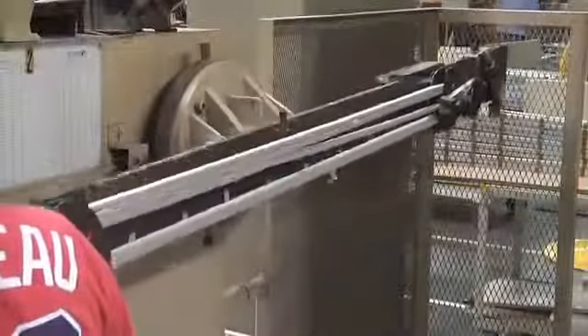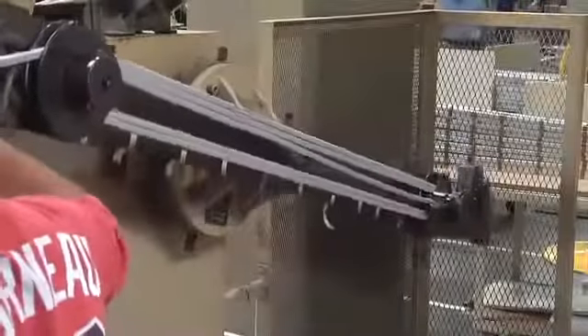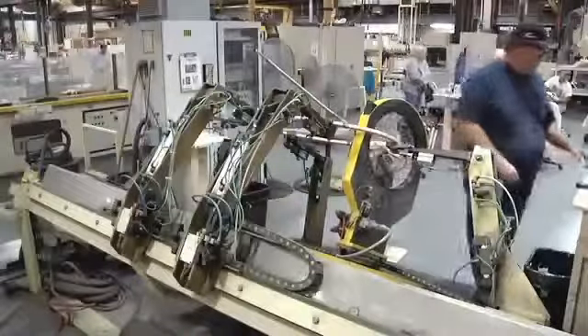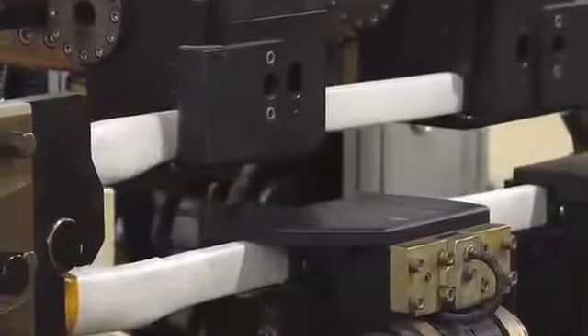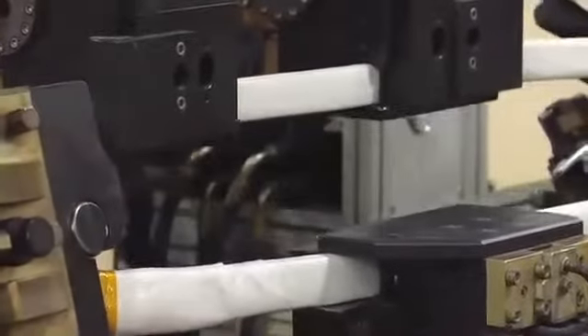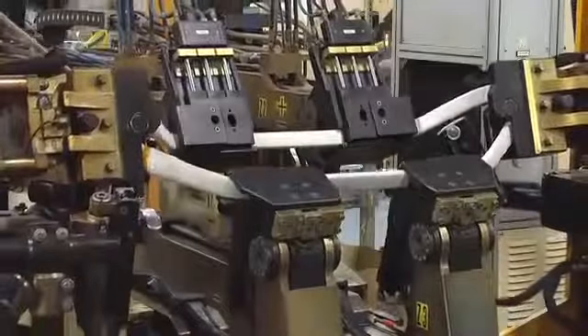A skeining machine rolls the wire into a loop. During the skeining process, a machine carefully wraps mica tape around the coil. The flat taping machine adds the ground wall tape to the outside of the coil to ensure insulation. After the coil is taped, it is formed to the proper geometry using a precise computer-controlled press process.